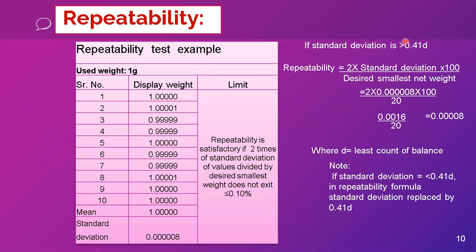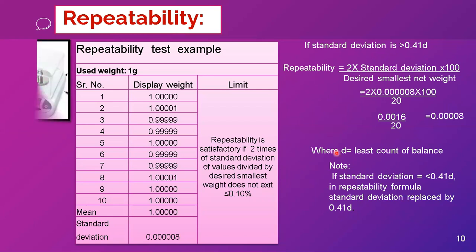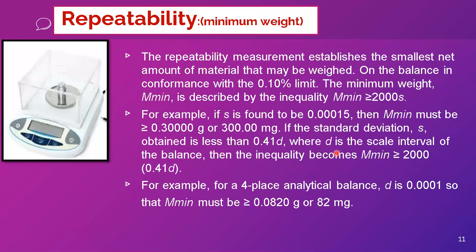There is one more condition: if the standard deviation is less than 0.41D — where D is the least count of the balance — then instead of the actual standard deviation, we use 0.41D in the formula. If 0.41 × least count is greater than the standard deviation, we substitute 0.41D in place of the standard deviation and apply the same formula.